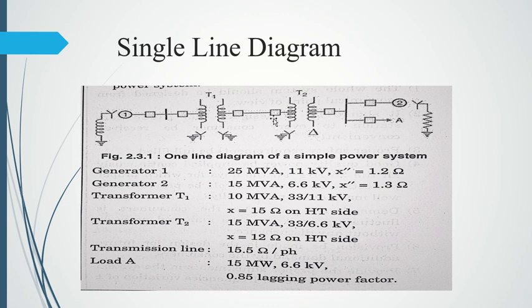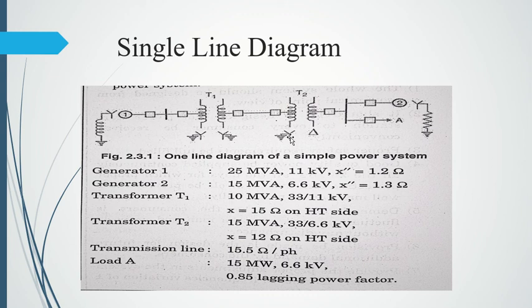Transformer T1 is rated 10 MVA, 33/11 kV, with a reactance of 15 ohms on the high-tension (primary, 33 kV) side. Both primary and secondary sides have grounded star connections. From T1, there is a circuit breaker, then a transmission line, then another circuit breaker before transformer T2. T2 is rated 15 MVA, 33/6.6 kV, with reactance of 12 ohms.